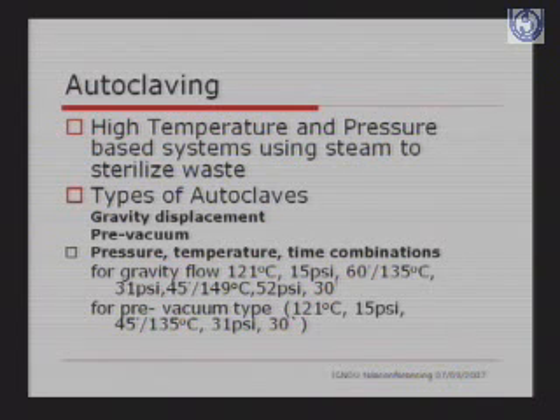Then we have gravity flow autoclaves. At a lower temperature, we have a 15 psi pressure for 60 minutes, and similarly if we are increasing the pressure and the temperature, the time duration goes down. Whereas for the pre-vacuum type, it takes a shorter duration: 121 degrees centigrade at 15 psi for 45 minutes, and 135 degrees centigrade at 31 psi for 30 minutes. So this is the standard that has been prescribed for autoclaving.